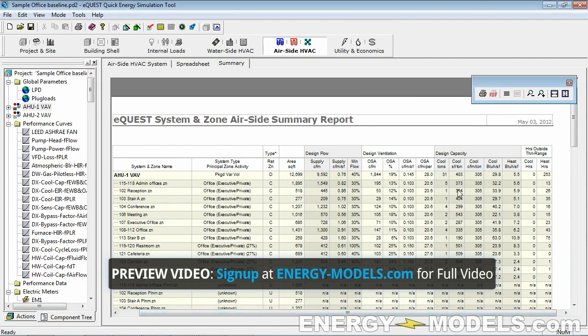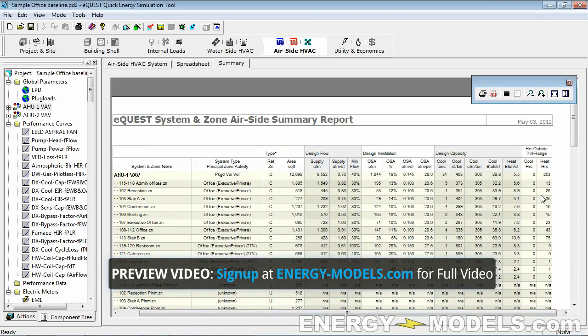We never did troubleshoot unmet hours on this, though we are under 300. The only difference is that this could not exceed the baseline by 50. So what's the number one reason for unmet hours — unmet heating hours?